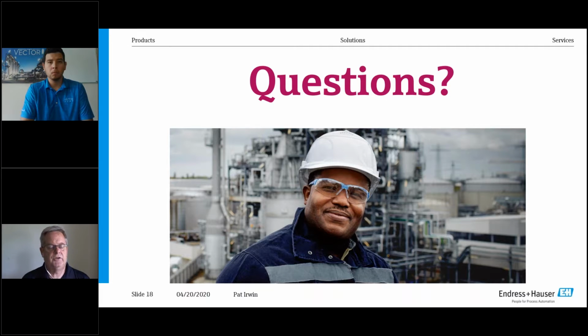The resonant sensor technology is a good technology. It's still being proven out there, but what they learned from going to that platform again was the silicon substrate base, to where you can now add the hysteresis into the calculation for the TPE. So when you're doing your total probable error, that is factored in, where historically it was not.